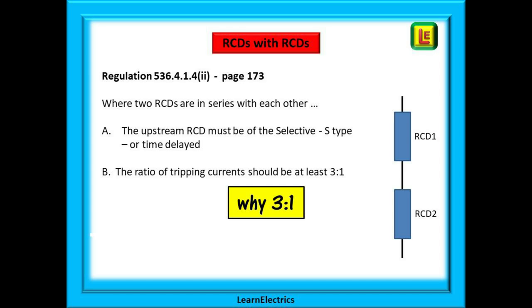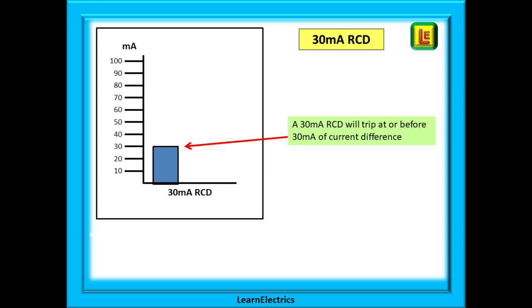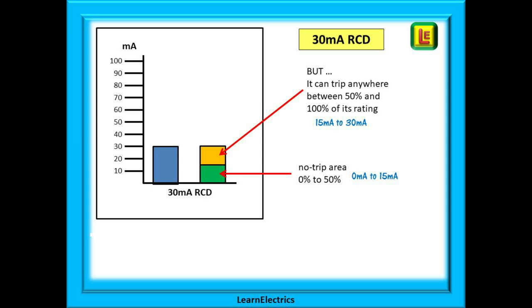But why choose a ratio of 3 to 1? If we look at a 30 milliamp RCD we know that it will operate when the residual current approaches 30 milliamps. The RCD is designed to operate anywhere between 50 percent and 100 percent of its rating which means that for a 30 milliamp RCD it could trip anywhere between 15 milliamps and 30 milliamps.